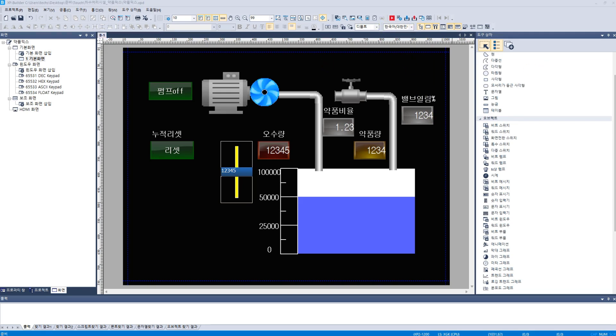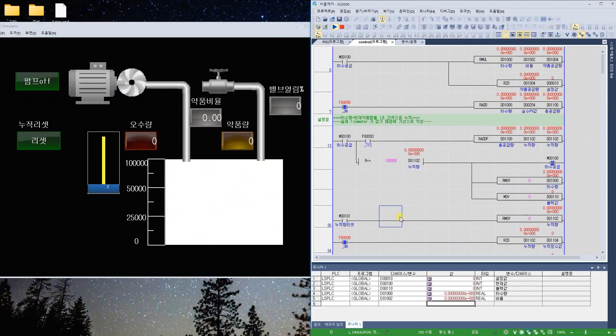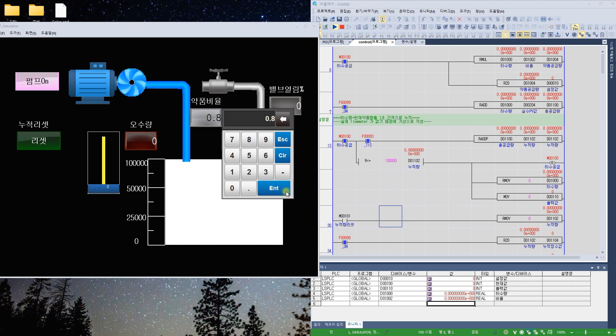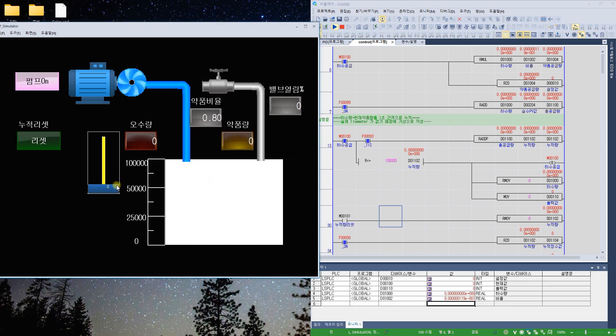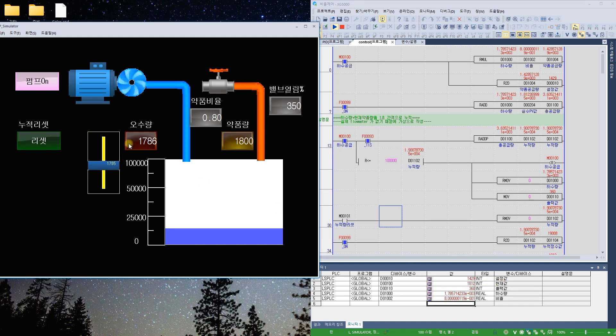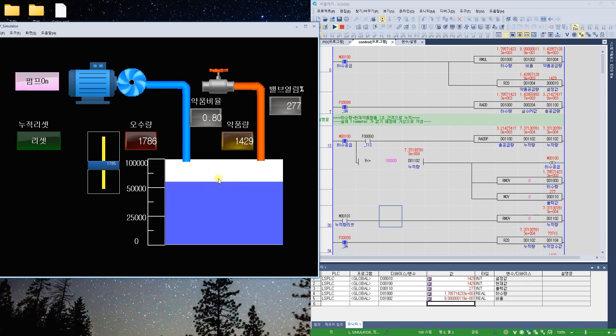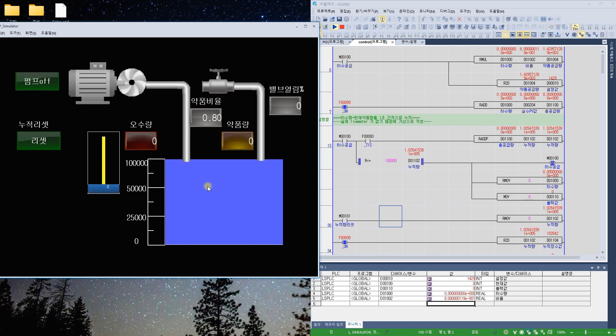Let me run the simulation again and operate it. I'll turn the pump ON and set the chemical dosing ratio to 0.8. The wastewater flow is supplied via slider. The set value based on this ratio is entered, and the PID operates to match this set value. These two values are combined and accumulated every 1 second to supply the tank — that's the HMI I made. Once it's full, the wastewater flow and pump turn off, and the chemical amount becomes 0.